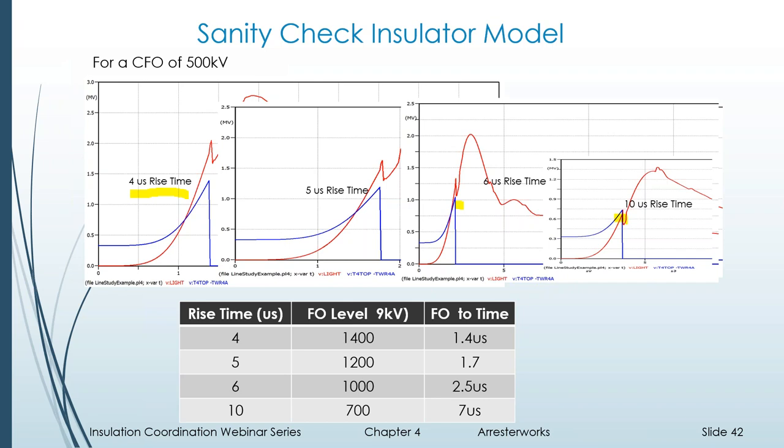So this tells us that, yes, it has a higher withstand for the shorter rising surges. We could plot that out, and it should look very similar to what the insulator withstand curve should look like. Again, just a sanity check.